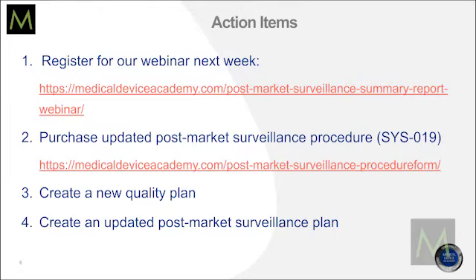You should also have an updated post-market surveillance plan. If you're CE marked, you've written it to make the Europeans happy — you might want to modify it a little to make the Canadians happy so it covers both aspects. Two things not on this list but important for any change: do an internal audit after you've made the changes, and have a management review of the internal audit results, identifying what you didn't do well and what needs to be done to fix remaining items before your MDSAP auditor comes back.